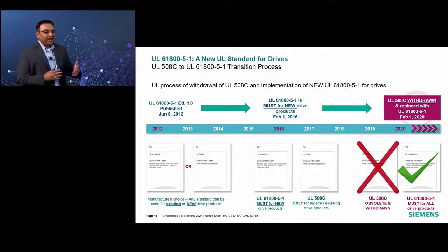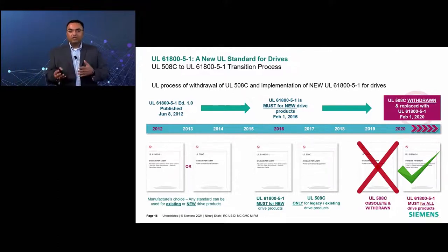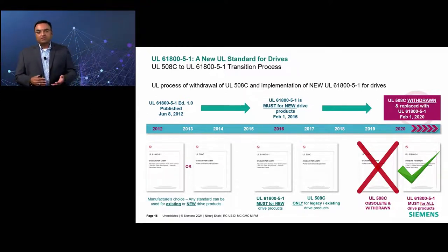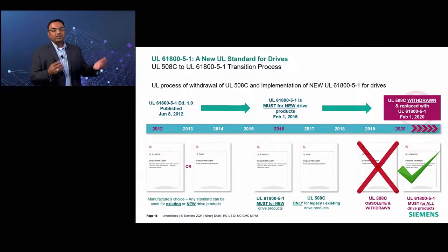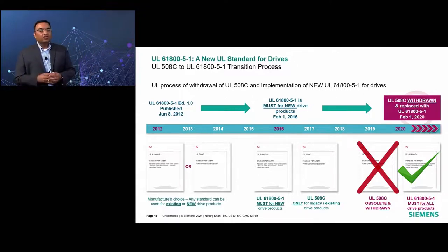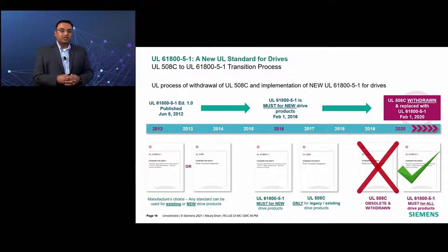It means that any replacement of the components within the existing 508C listed drive, for example, a DC bus capacitor or IGBT or a diode, may require a complete redesign, complete overhaul of the design, and retesting and recertification according to this new standard 61800-5-1.